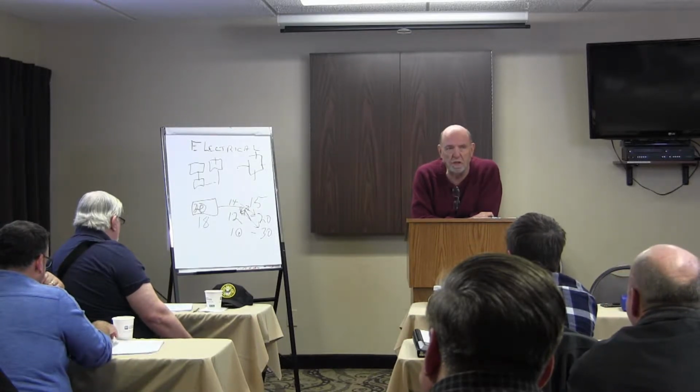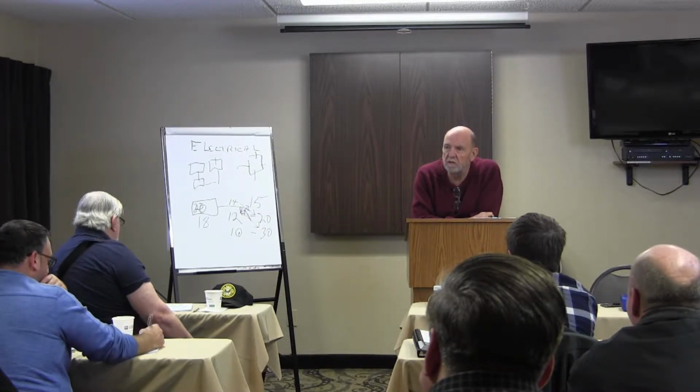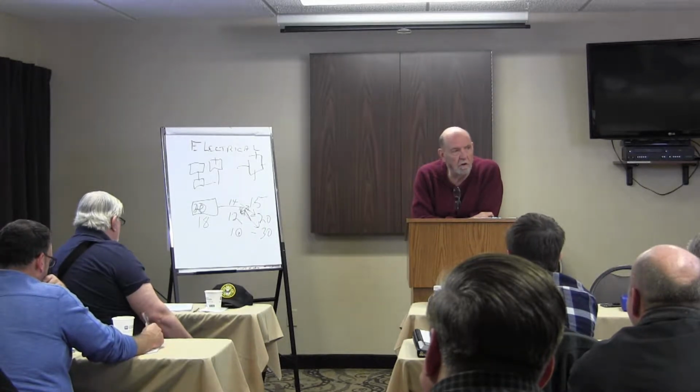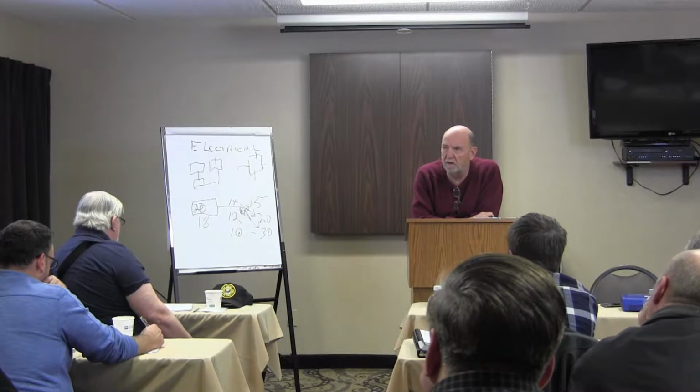I don't care what's on a 15 amp breaker. There's no wire in the house that's too small for the 15 amp breaker. All I care about is what's on the 20 amp breaker.